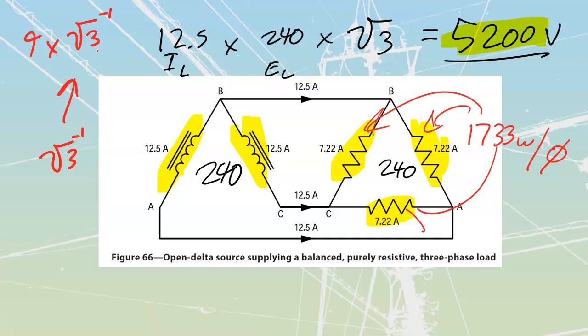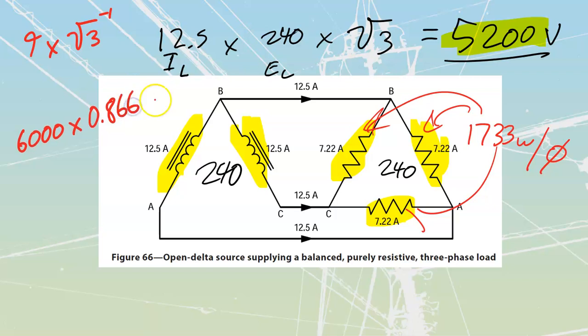The other way that you could look at this is you could say of the 2 windings that I have over here, the 2 windings should have 6,000 VA that they should be able to put out. But if I take that 6,000 and multiply it by 0.866, that's going to get me to 5,200 as well. So either one of these works perfectly fine for determining what the total kVA capacity is going to be of this, whether you want to go with the 86.6% of the 2, or if you want to go with the 57.7% of the entire bank, or if you just want to go through all the math and verify these.